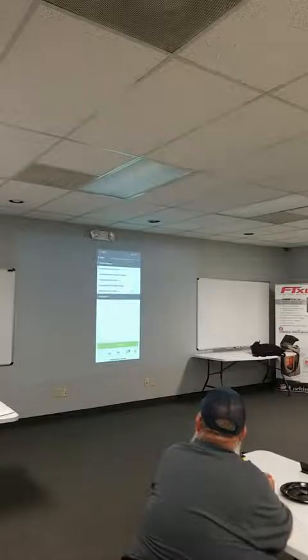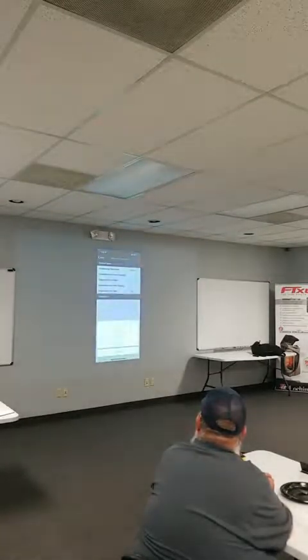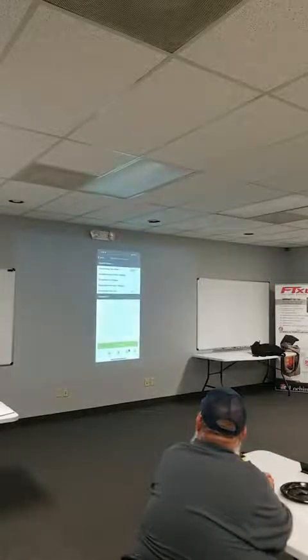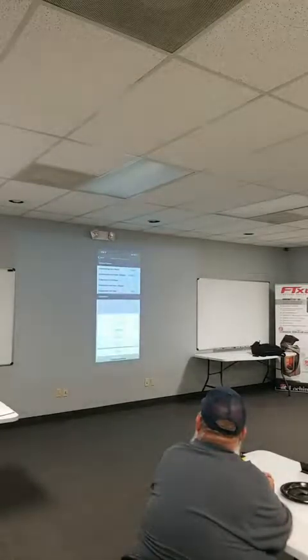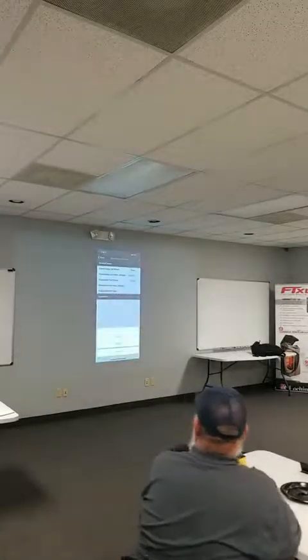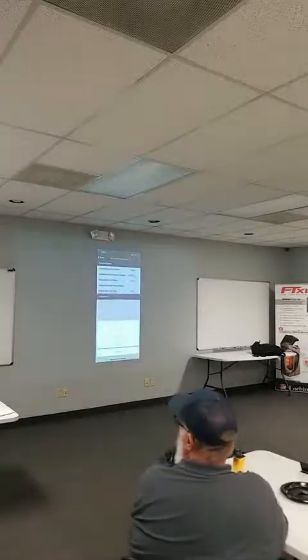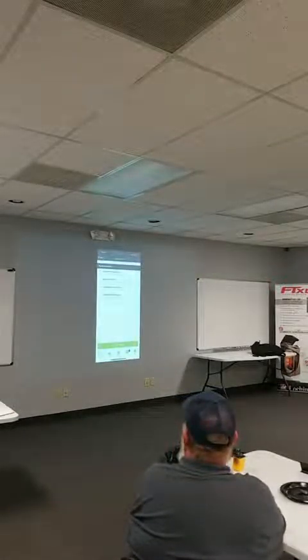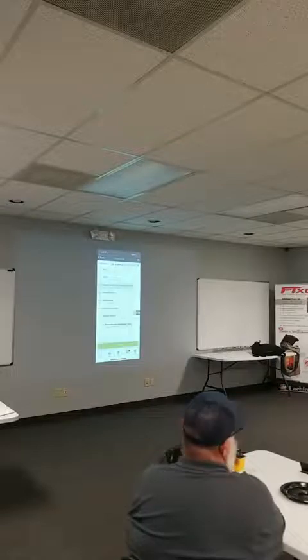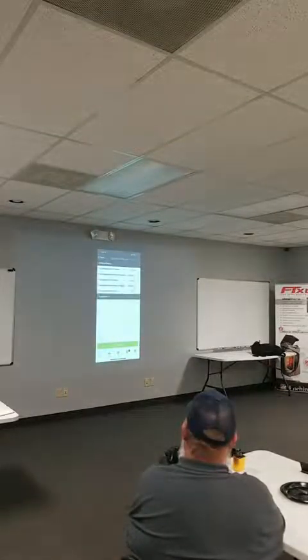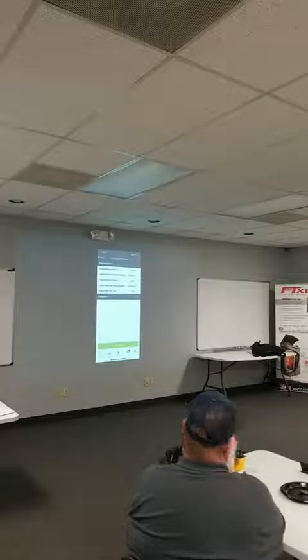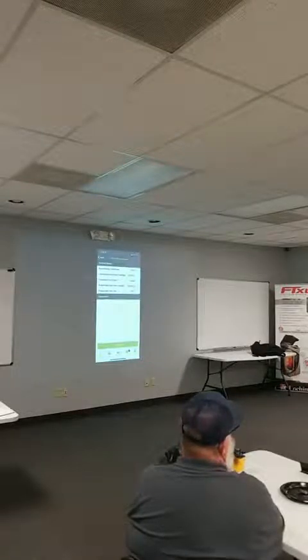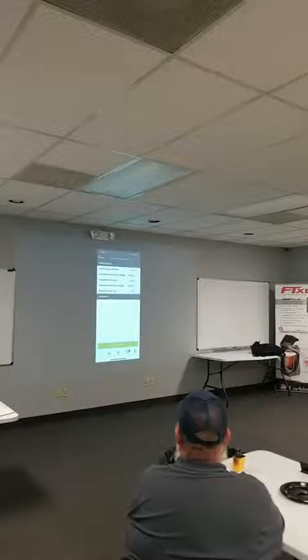Electrical information, condensing unit: single phase, 208, 230. Or three phase, 208, 230. Evaporator fan type: is it single phase or three phase evap? It's probably single phase. Is it going to be three? No, it doesn't have to be. A lot of Trane stuff uses single phase motors on the evaporator fan. On the littler motors, anything under a horsepower is typically single phase. They do that on condenser fans too.